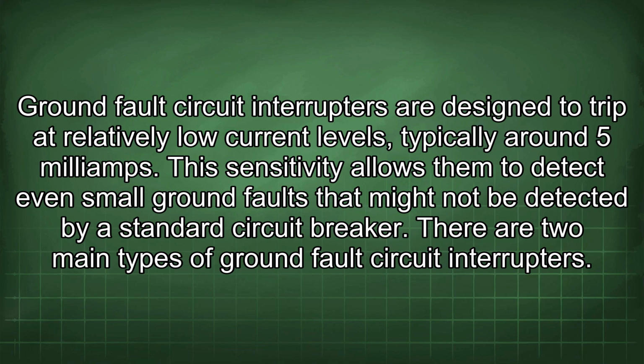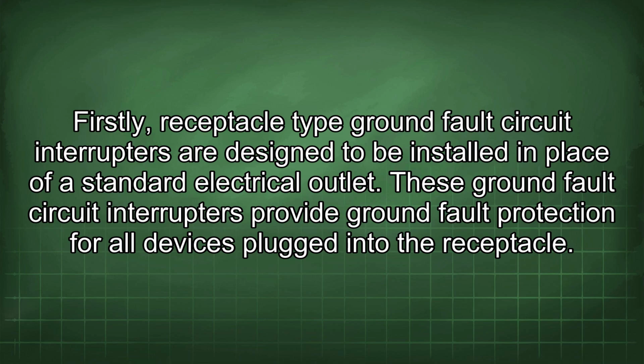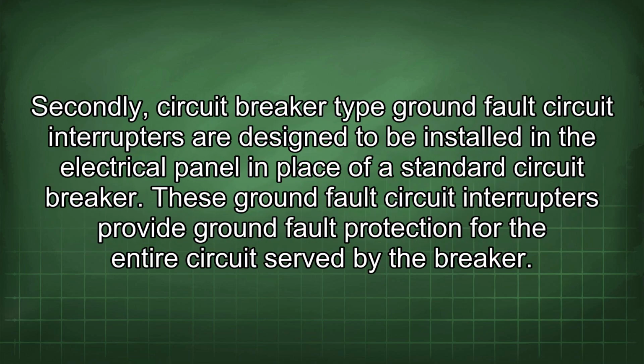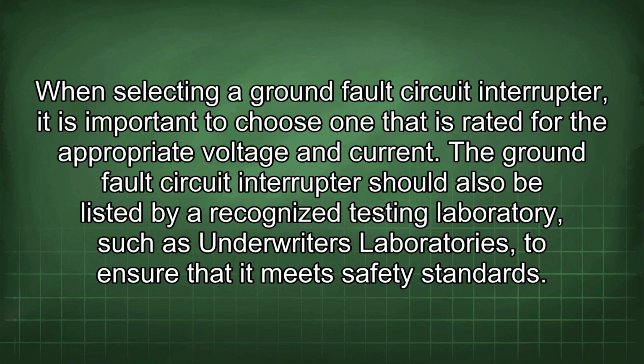There are two main types of ground fault circuit interrupters. Firstly, receptacle-type ground fault circuit interrupters are designed to be installed in place of a standard electrical outlet. These ground fault circuit interrupters provide ground fault protection for all devices plugged into the receptacle. Secondly, circuit breaker-type ground fault circuit interrupters are designed to be installed in the electrical panel in place of a standard circuit breaker. These ground fault circuit interrupters provide ground fault protection for the entire circuit served by the breaker. When selecting a ground fault circuit interrupter, it is important to choose one that is rated for the appropriate voltage and current. The ground fault circuit interrupter should also be listed by a recognized testing laboratory, such as Underwriters Laboratories, to ensure that it meets safety standards.